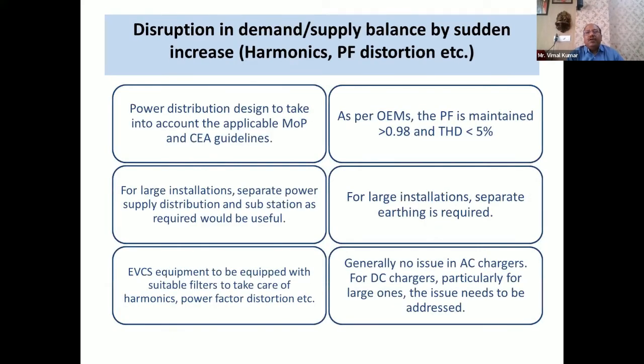Another aspect is harmonics and power factor distortion. First, whatever guidelines exist for individual equipment standards and CEA guidelines, if implemented, will take care of site installations. During discussions with manufacturers, we found it's preferable to have a totally separate distribution scheme for the EV charging system, with separate earthing, which helps.